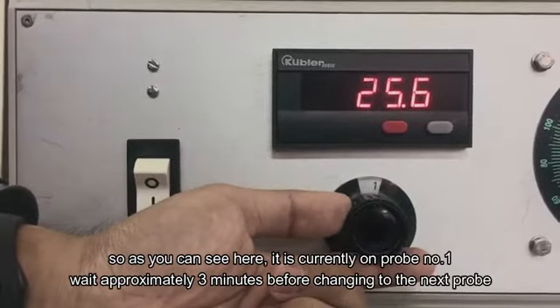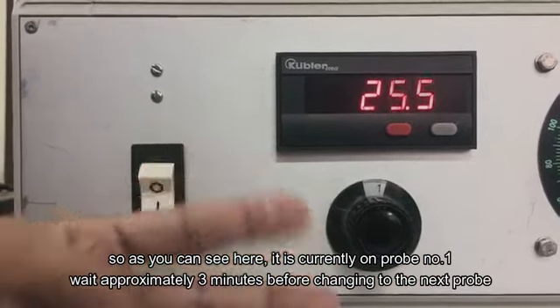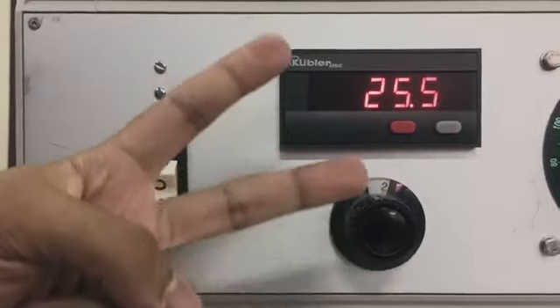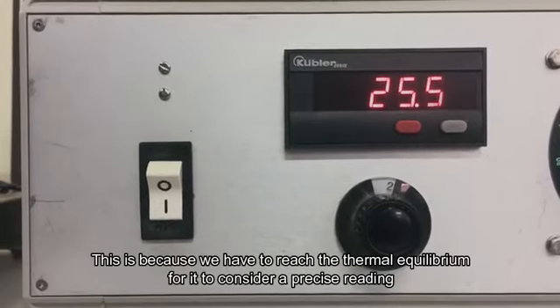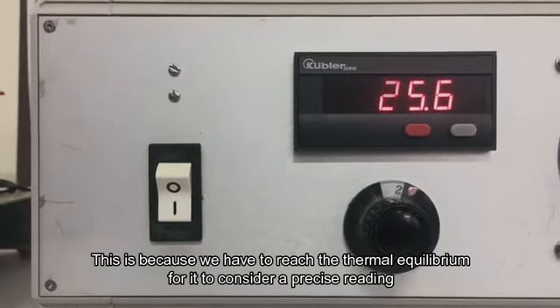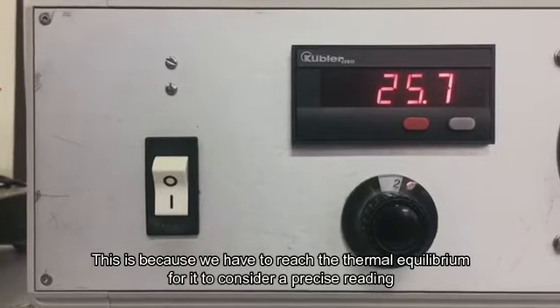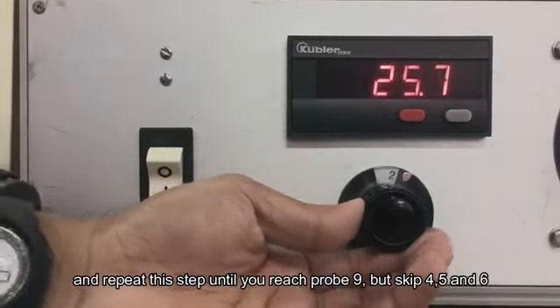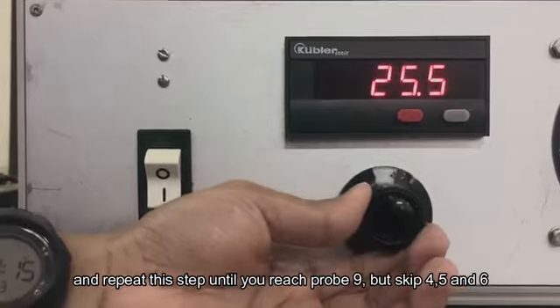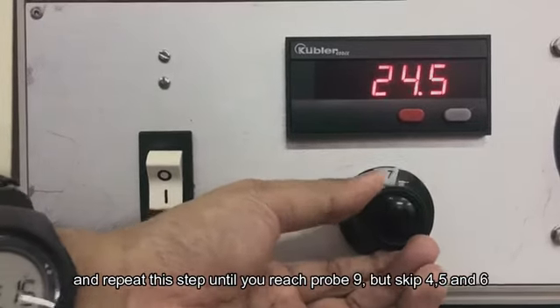As you can see here, it is currently on probe number 1, wait approximately 3 minutes before changing to the next probe. This is because we have to reach thermal equilibrium for it to be considered a precise reading. Repeat this step until you reach probe 9, but skip 4, 5, 6.